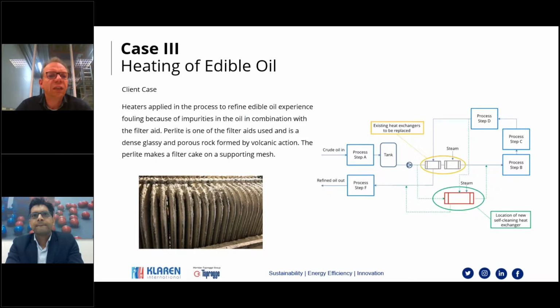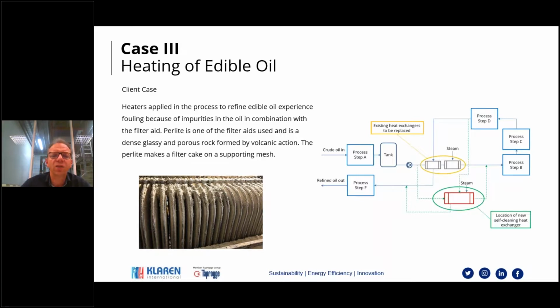The third case is a heater and heat exchanger for a plant, a refinery, refining edible oil. So edible oil, before it can be shipped to consumers, needs to have certain treatments. Some components need to be taken out, it needs to be deodorized, it needs to be filtered. And in this plant, which they call the refinery, there is an issue with the heat exchangers that heat the oil before it goes to one of the process steps. You see them in the yellow circle.